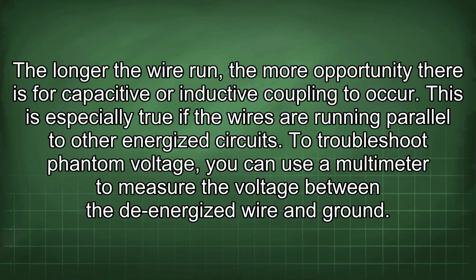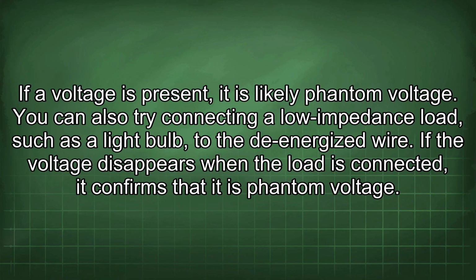To troubleshoot phantom voltage, you can use a multimeter to measure the voltage between the de-energized wire and ground. If a voltage is present, it is likely phantom voltage. You can also try connecting a low impedance load, such as a light bulb, to the de-energized wire. If the voltage disappears when the load is connected, it confirms that it is phantom voltage.